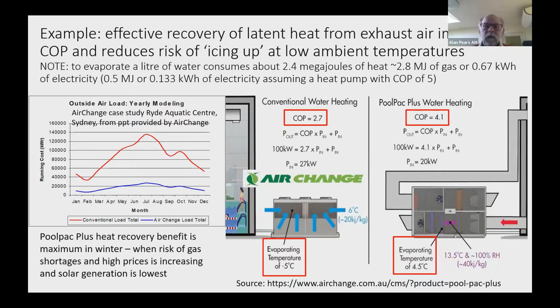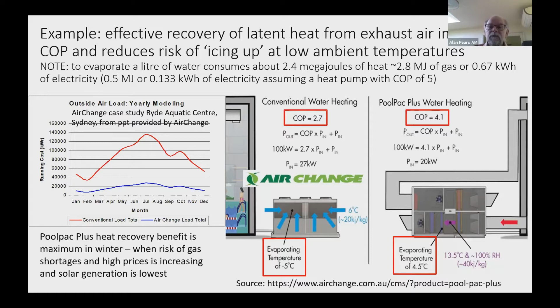Another important thing is that the energy recovery from waste heat shows you're actually saving most of the energy when it's colder in winter. This is good for two reasons. First, rooftop solar is nowhere near as plentiful in winter as in summer, so saving most of the energy here fits well with your PV situation. Second, particularly in the southern parts of Australia, we're looking at winter gas shortages in the next few years, meaning higher prices and more concerns about gas availability. So the characteristics of this heat recovery system and heat pump fit our new renewable energy sources very well, solving our gas problems and reducing energy consumption.